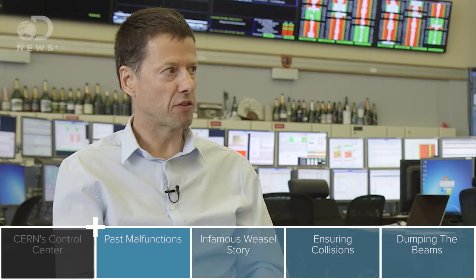Back in 2008, we were just commissioning the LHC with beam for the first time. We'd actually circulated beam in both directions for the first time on the 10th of September. Nine days later, we were finishing off some powering tests. We had about 8,000 amps in the main magnets and a short developed in the interconnect between two magnets. This opened up, started arcing, and caused a helium leak, which flooded helium into the magnet space. We had a train wreck on our hands — the screens really did go red. We had hundreds of meters of magnets ripped off their jacks. These are 30 tons each. About 50 magnets had to come out, be refurbished and repaired, and we were off for over a year. That's as serious as it's got so far.